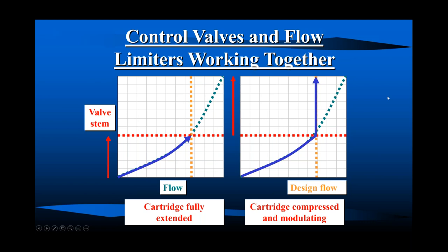Another question for you, John. Sure. We might be jumping the gun here with this, but how does this compare to a PICV or a pressure independent control valve? Well, we'll get to that last, but to jump ahead a little bit, a PICV is a flow limiter. So we'll talk about how that affects everything else in your system. Excellent product, right? A PICV would probably react to this differential pressure increasing before the flow limiter has to come into play. But yes, a PICV modulating control valve is also a flow limiter. Gotcha. Thank you. Okay, so yes, they work together. And yes, a PICV is a flow limiter and control valve in one body.